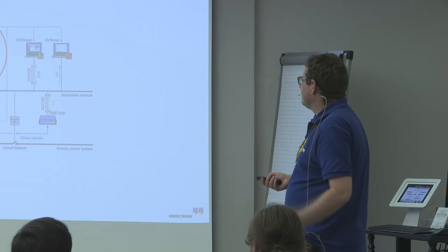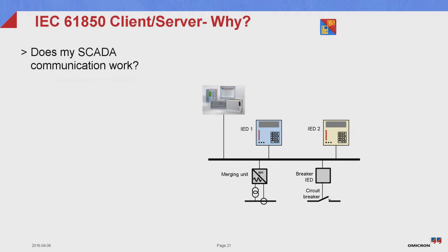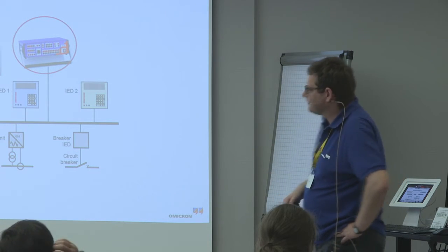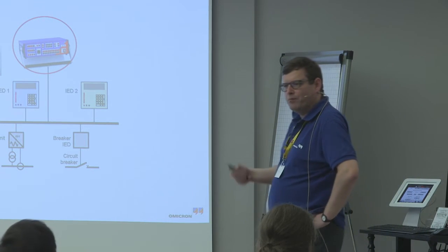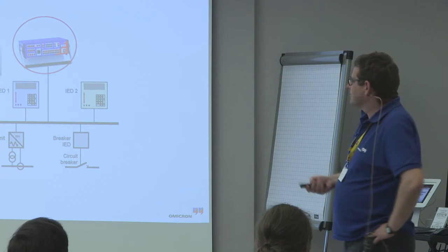And I want to explain to you how it works. So we really say that now it makes sense that I do not only have the SCADA system or any other IEDs working as a client. I want to try this out also with protection testing. So the idea is the protection test set will play something like a SCADA system, embed this into protection testing, not to take over the entire task, of course. You saw how complex it is. But for this little task, protection testing, to really take this over.